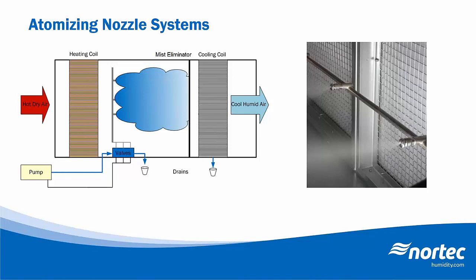Now, due to the requirement for that treated water, the total water consumption for an atomizing system will typically be higher than for a comparable evaporative media system operating on potable water. And that's simply because of the concentrate, the wastewater that's generated from the water treatment system itself. So this definitely needs to be considered in the total cost of ownership when selecting an adiabatic technology.